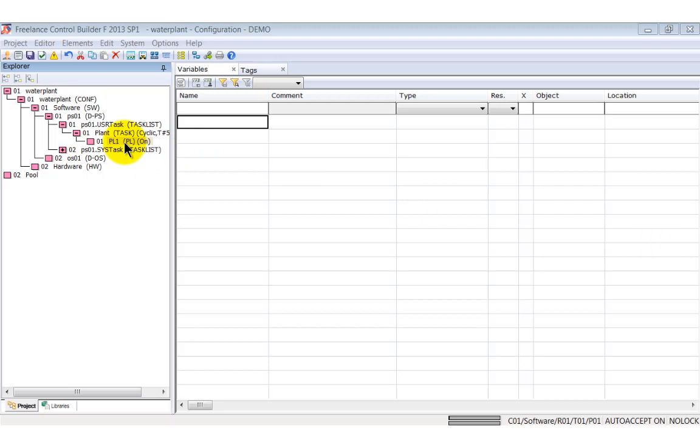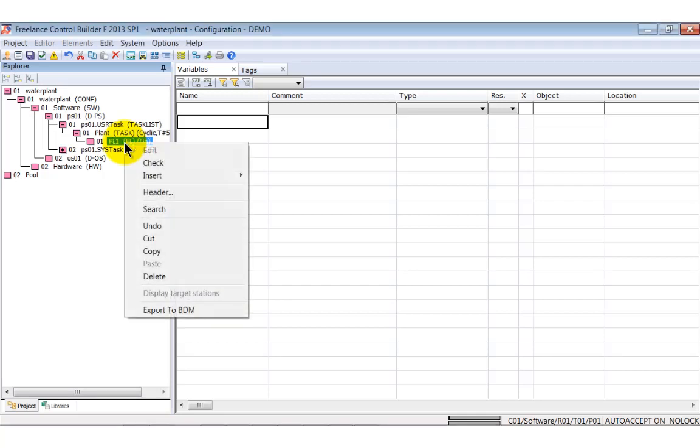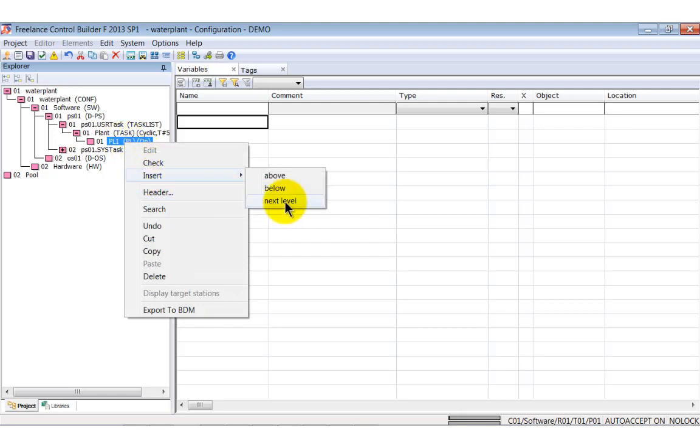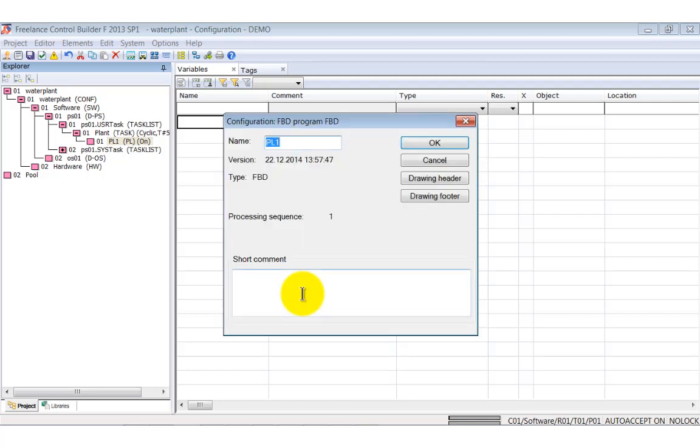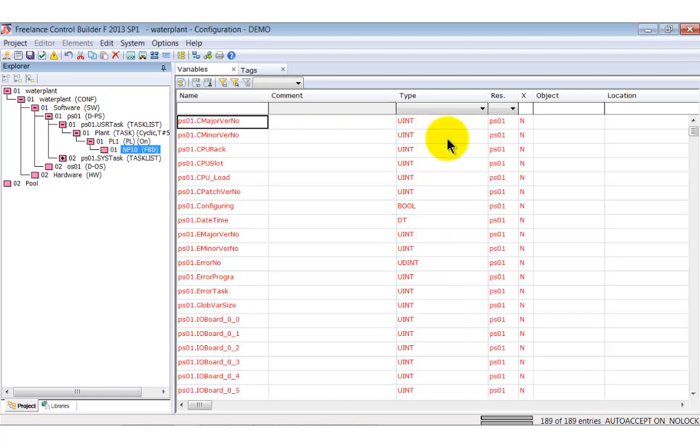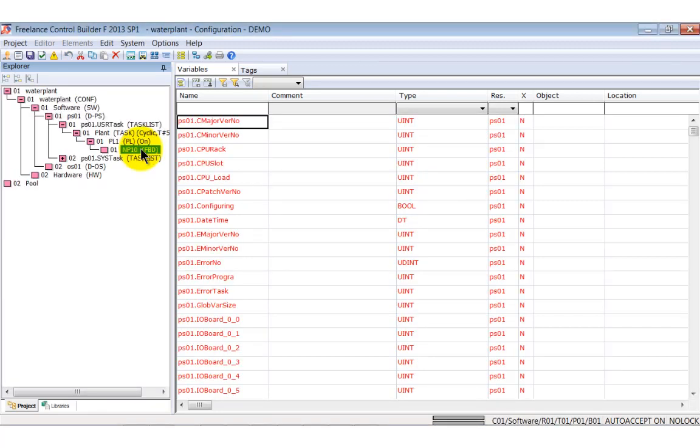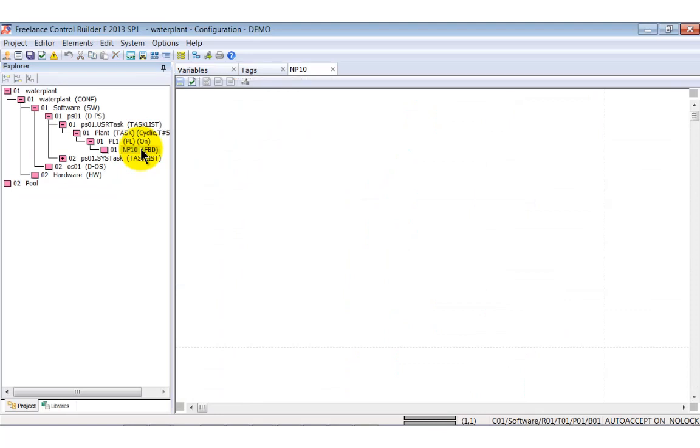A program list is simply a structural element to take several function block diagrams or other programs. Insert a function block diagram under the program list. For this purpose select the program list, open the context menu and select insert next level. Select function block diagram FBD and name it NP10. Now the structure we need is ready. Double click the function block diagram and open the editor.